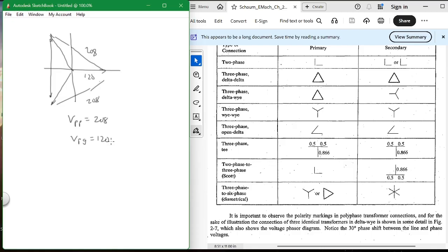Now what is the difference between 208 and 240, or 230, or whatever the difference is there? 15 volts, 20 volts, that's enough to cause motors to not work, but most motors and most circuits now will work with either 208 or 240. So you can get a motor that will turn at either 240 or 208. And if you don't, how do you get 240 out of 208?